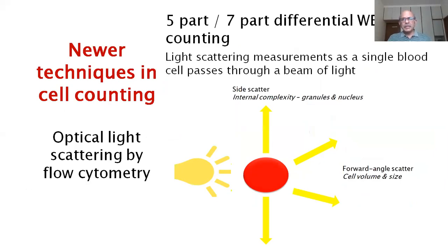I told you there are two major principles on which the whole business of automated hematology analysis is based. Sometime in the 1950s, Mr. Coulter came up with this principle, which is known as the Coulter principle, which I have already alluded to. So it is eponymously known as the Coulter principle. The newer generation machines, which make life much easier for us and for the pathologists also, are based on flow cytometry. The principle is very simple.